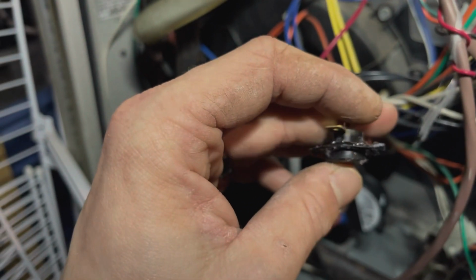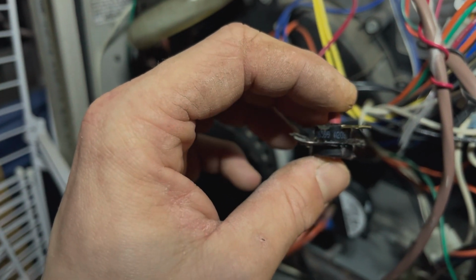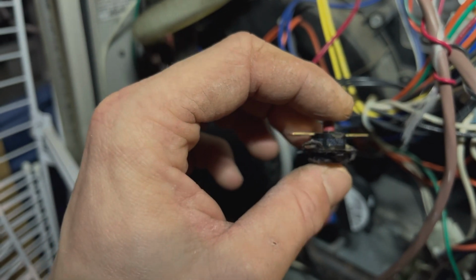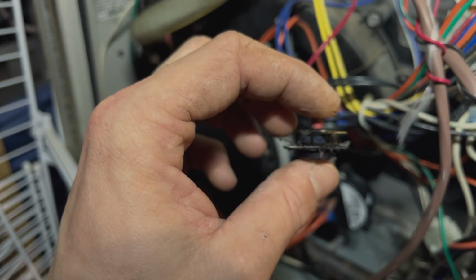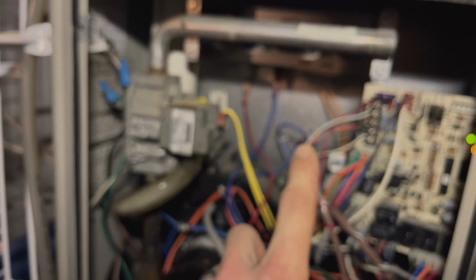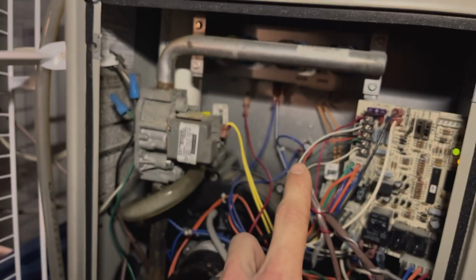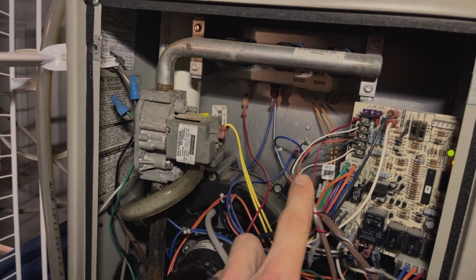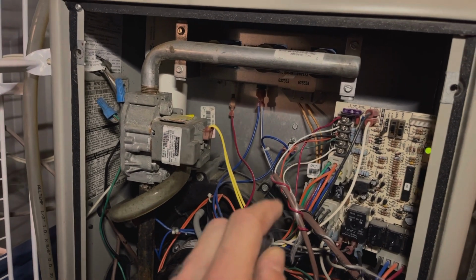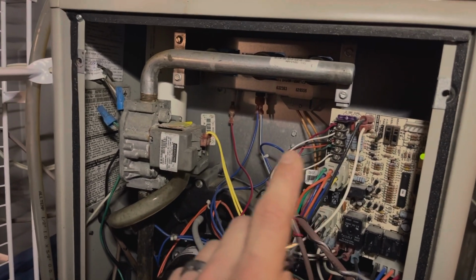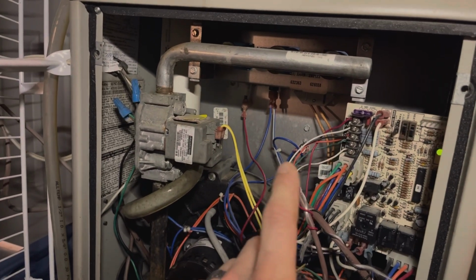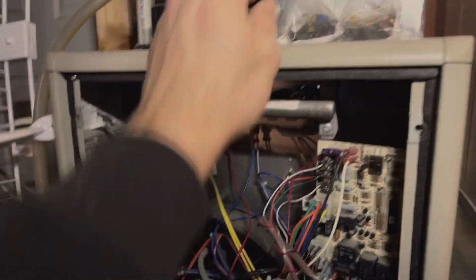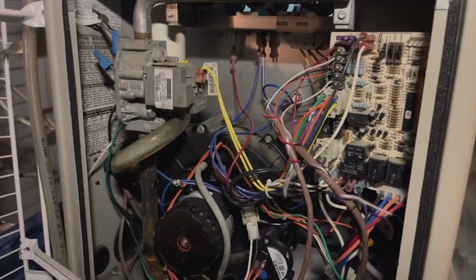Now, I had another one in here, and I believe it said L180 minus 40 F. So that means it kicks on the blower motor at 180 Fahrenheit, and it kicks it off when it drops 40 degrees Fahrenheit, so it kicks it off when it's 140. It doesn't mean it kicks it off at 40. It means you do 180 minus 40. So that's how those work.